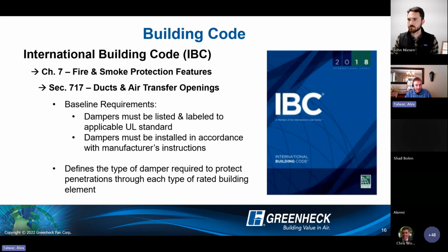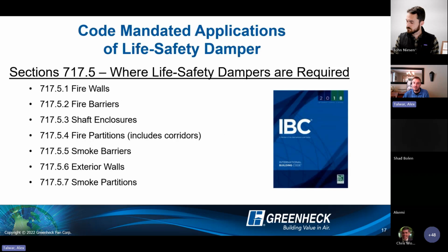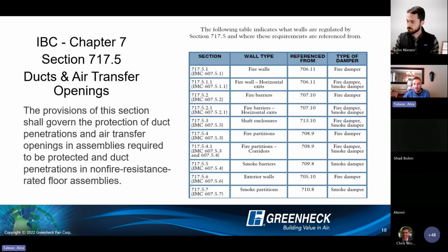These are really just reference slides here. In the International Building Code, if you are curious, section 717 is where the damper portion is called out, in ducts and air transfer openings, and it really defines a type of product for each category of construction. So this slide here is really my favorite reference slide, so I always like to include this one. If you want to take a screenshot or something, you're more than welcome to. But of course, if you have access to the International Building Code, section 717.5, you will find all of this information in there, dictating what type of product you need for what type of construction.